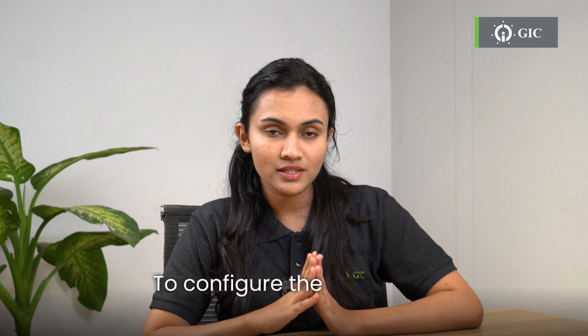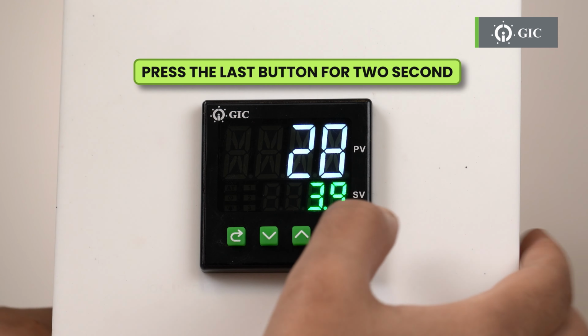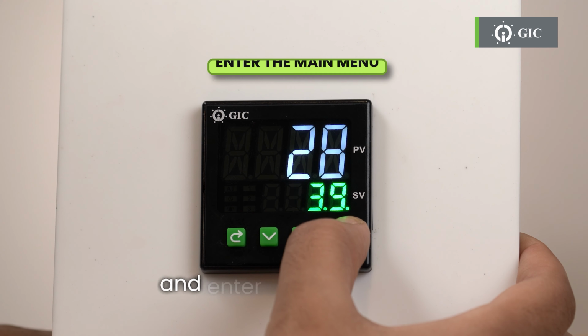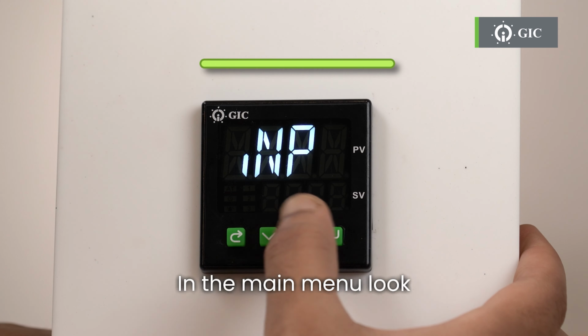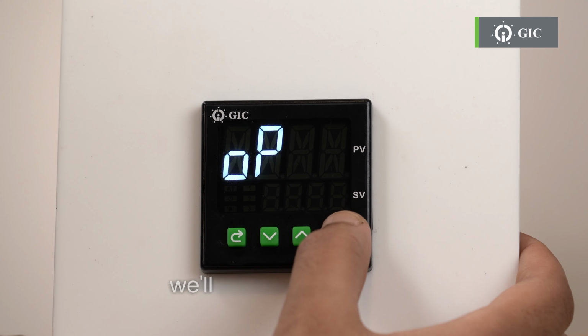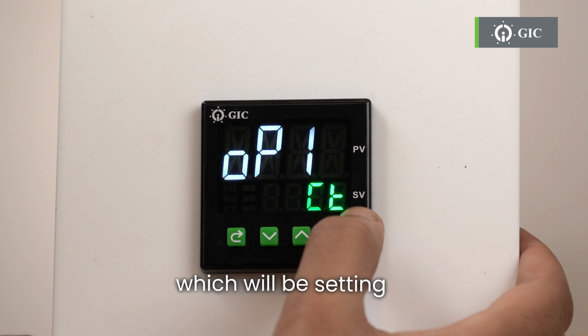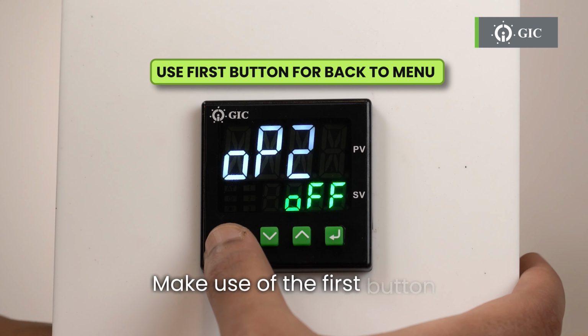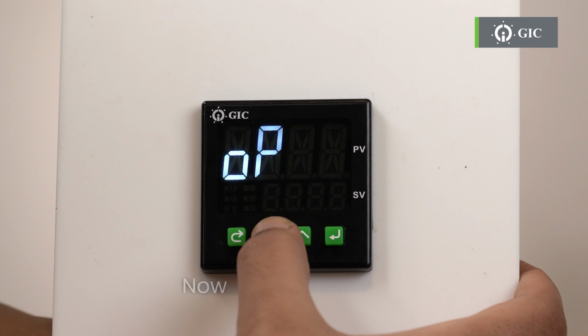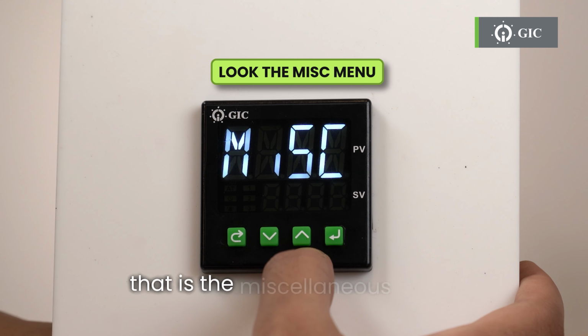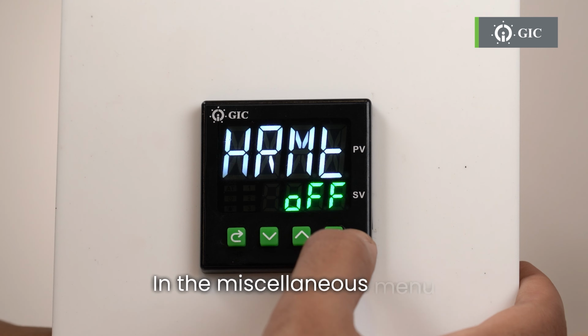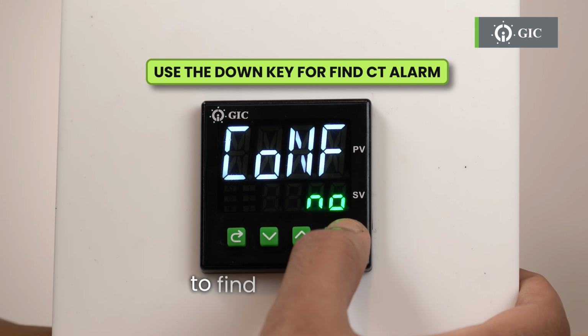To configure the CT alarms, we need to make use of the last button, press it for 2 seconds and enter the main menu. In the main menu, look for the output menu, within which we'll find the output 1, which will be set at CT. Make use of the first button to come back to the main menu. Now look for the MISC, that is the miscellaneous menu. In the miscellaneous menu, use the down key to find the CT alarm.